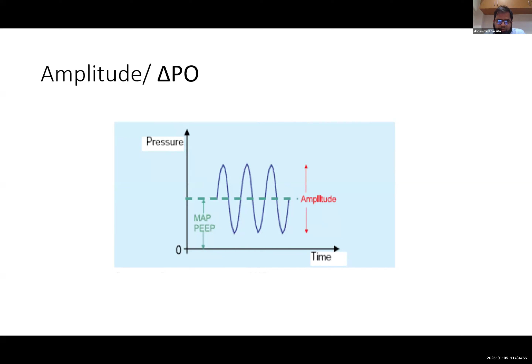So you will start with at least double the MAP, or around 20 to 30, and then depending on the baby's CO2 values, you will do a blood gas after 1 hour, and then depending on the CO2 values, you will adjust the amplitude. If you give more amplitude, the delivered tidal volume will be more, and the baby will have better ventilation. So if the baby has higher CO2, you will increase the amplitude, which will lead to CO2 washout.